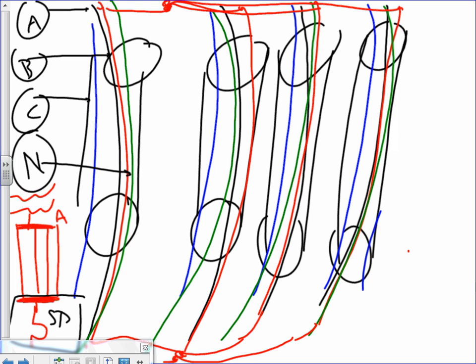How many conduits do we parallel? Four of them. Here's the four. And then what do they do with them? They go from one side here to the other side, guys. They tie the phases together. So all the phases, the four phases of A on both sides, will be tied together and tied to the equivalents. That's what paralleling is. So I have four sets. Each set is going to have three conductors, number 600 kcmil, and one conductor, what's the conductor? The neutral, number 2 AWG.